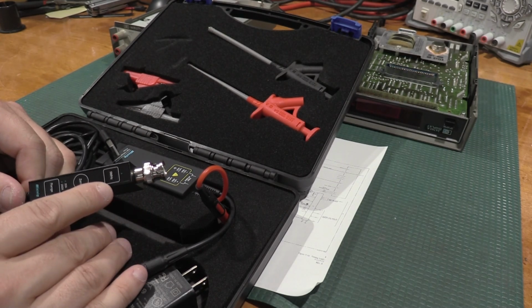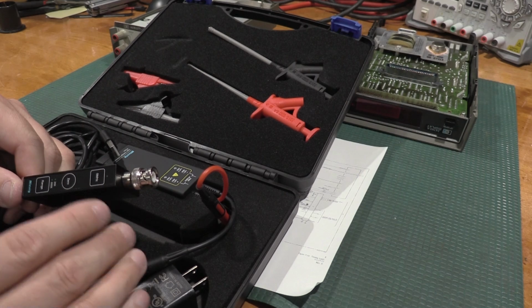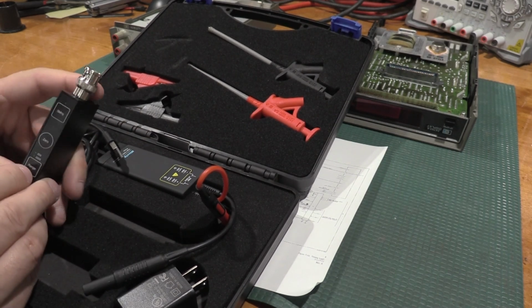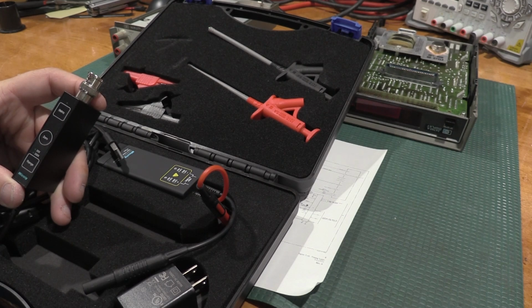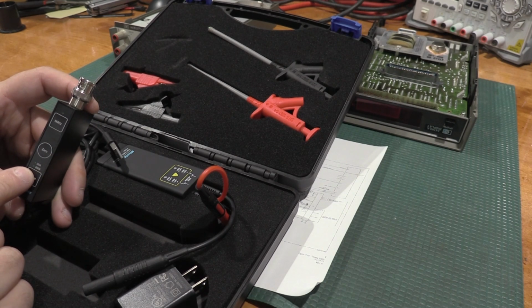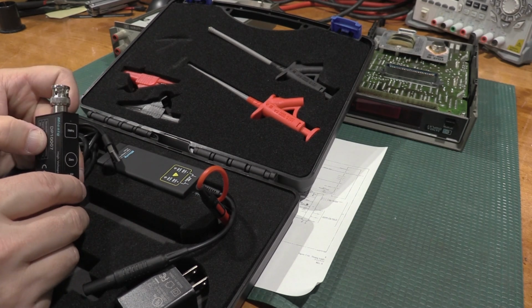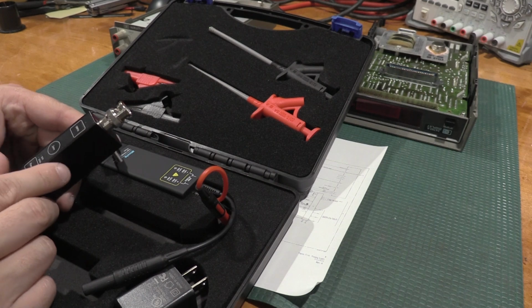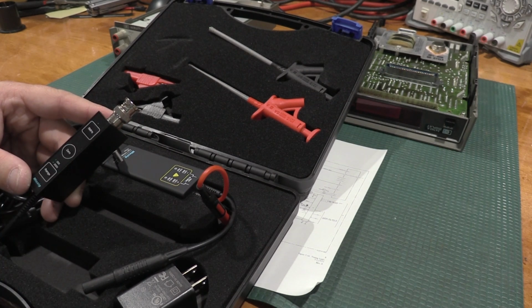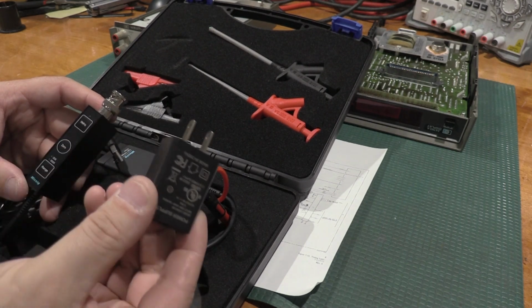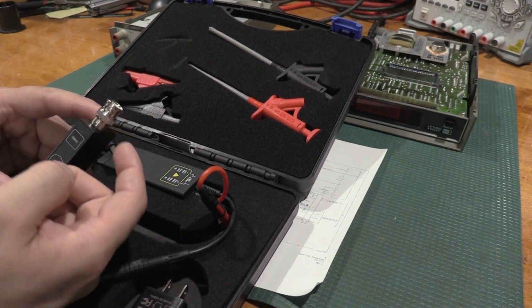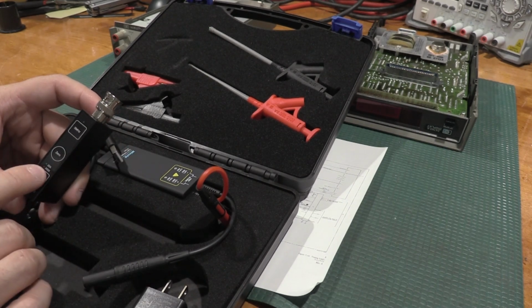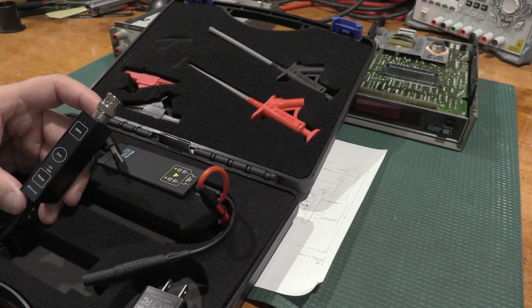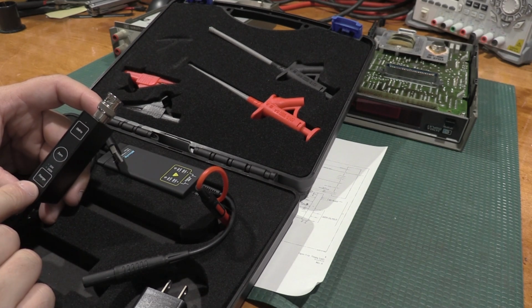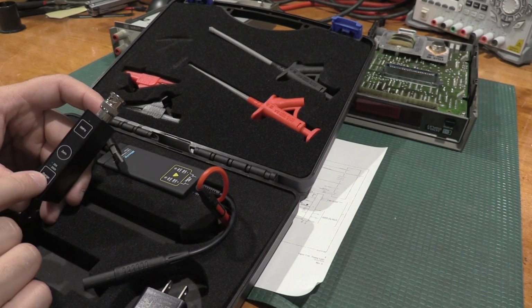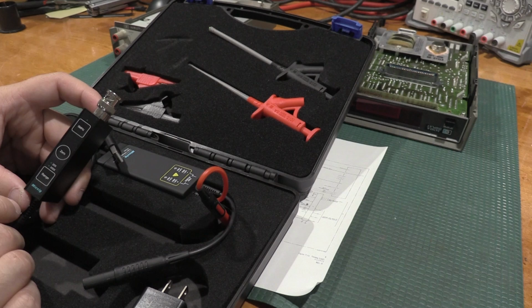Now, I believe I did it with the 5 megahertz limit turned on to cut out the noise, but also the reason to use the Rigol was to get the ranging right. This is a 20x and 200x probe. It's the DP10007. It will work with a Tek scope, not a problem, as long as you use the external power brick to turn the circuits on, because it's designed for 1 megaohm up here. But with this 20x and 200x, the display readout's going to be wrong, the switching's going to be wrong, so you'll have to do some compensation math to get the ranging right. On the Rigol, I can actually set 20 and 200x, so I can get the ranging right.